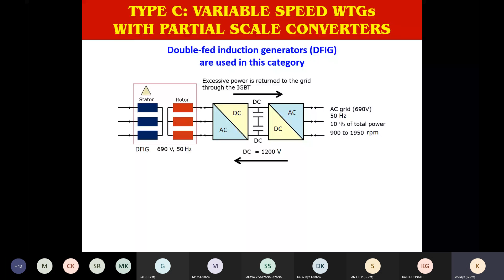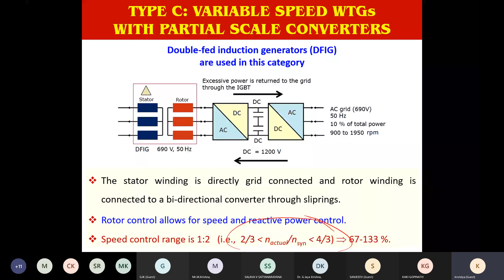So normal range is about 30%. That means the speed control range of this machine is in the range of 66% to 133%. That is about 66% of speed you can control, and it is very good. But that is not the perfect one or the ideal one. Commercially, it is very popular. About 75 to 80% of wind turbines commercially running use this doubly fed induction generator principle.